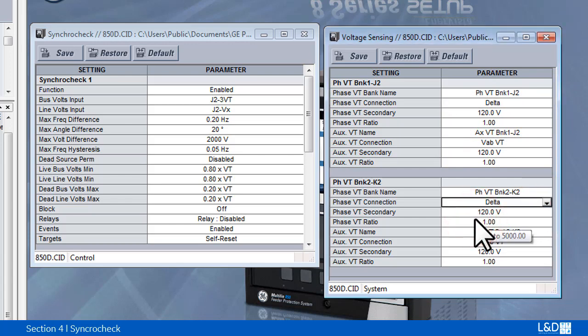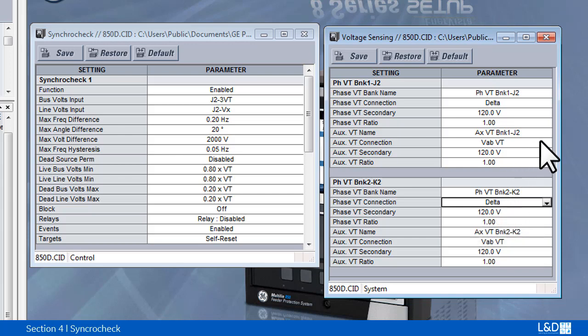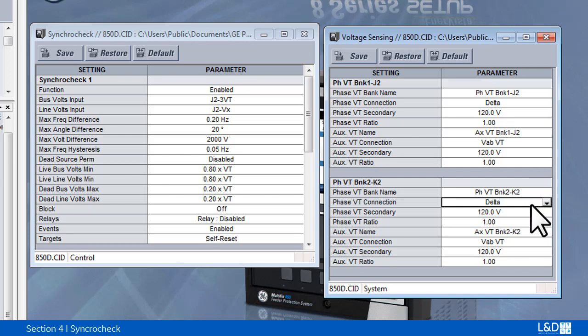If both sides are single-phase auxiliary VT input, then both auxiliary VT connection types must match. For example, if the line auxiliary VT type is VAB, then the bus side auxiliary VT should also be VAB.